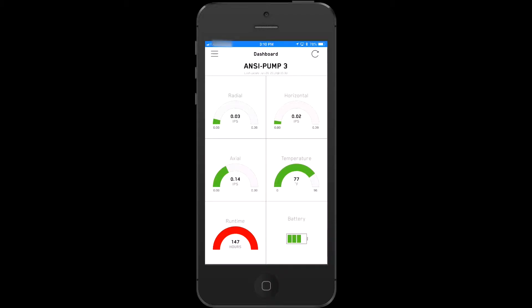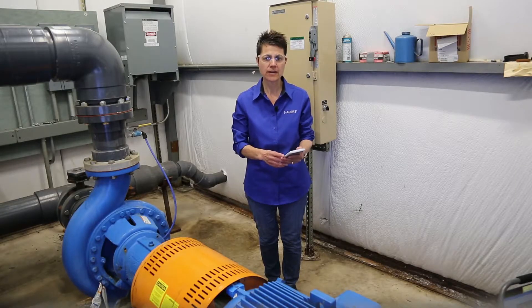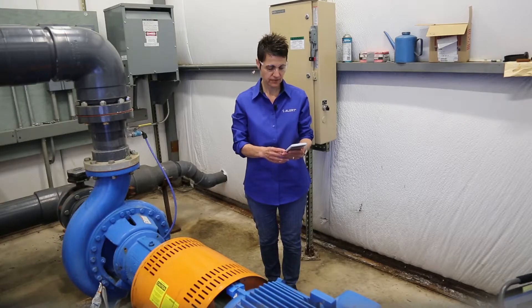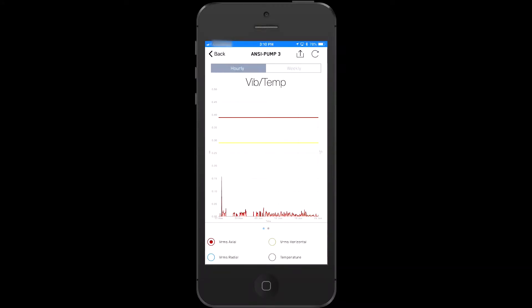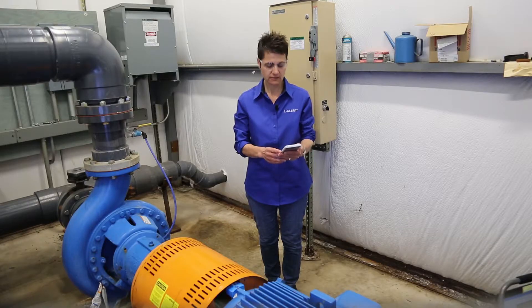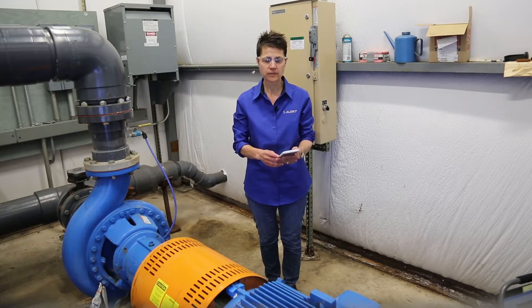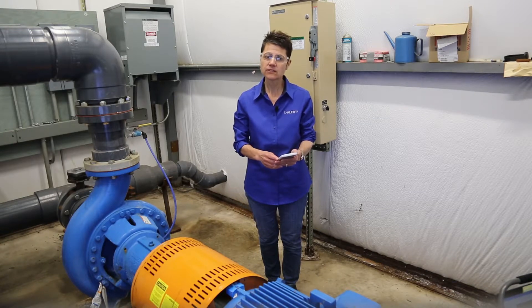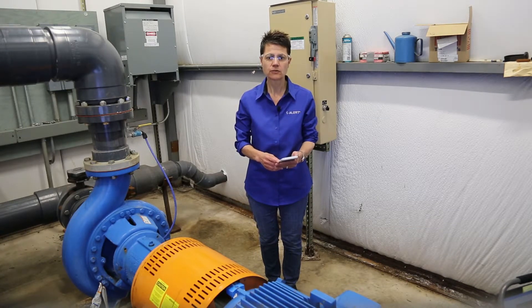Here's the dashboard that tracks overall vibration in all three axes, the temperature, the runtime, and the battery life of the iAlert. Here's all the trend data you've never been able to see before. And what's this? A spike. It happened last Tuesday at 2 a.m. You know that because everything has a timestamp, and that's really powerful.